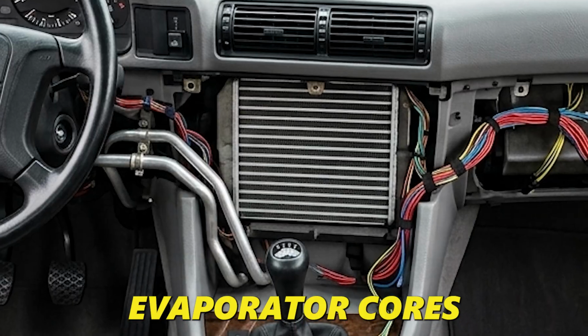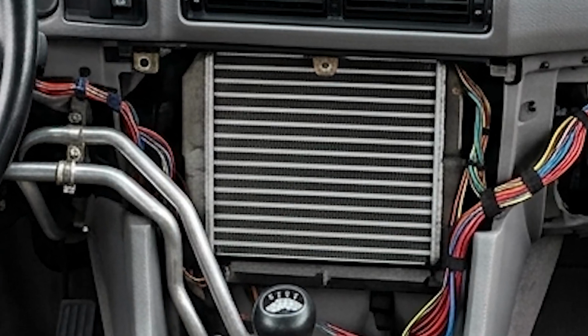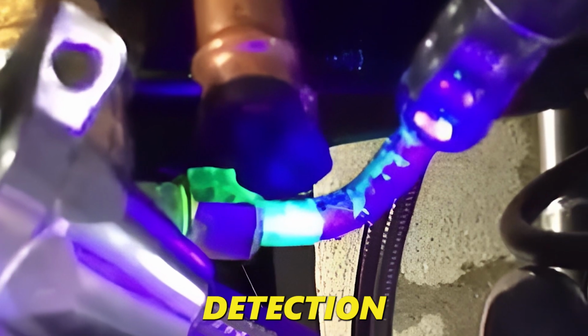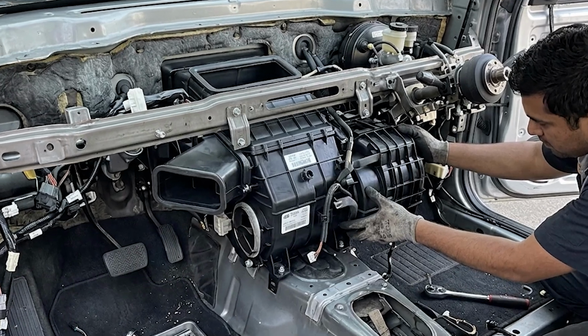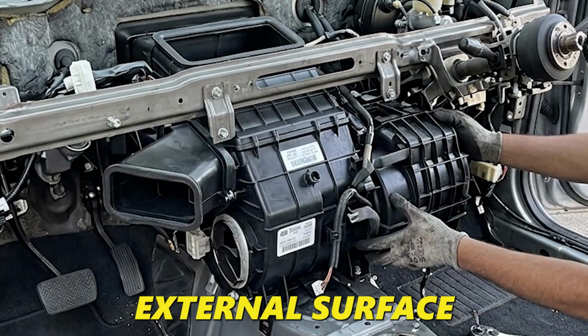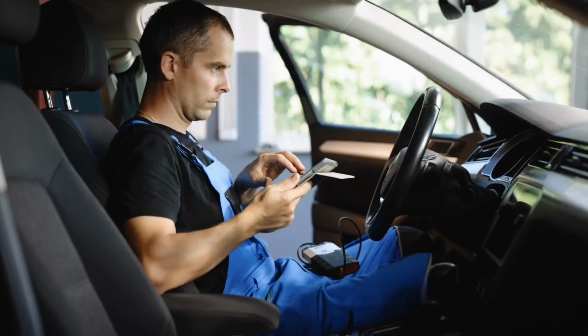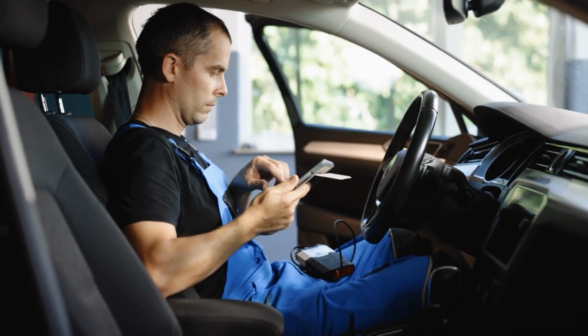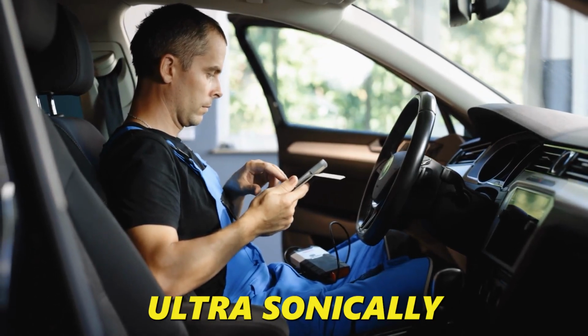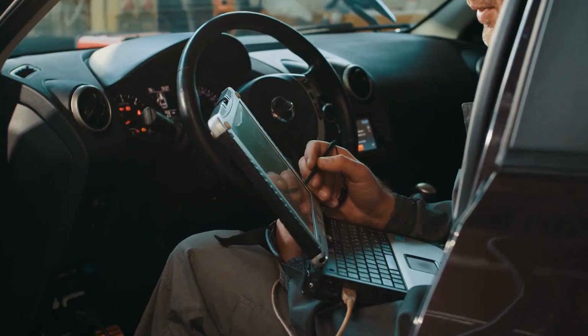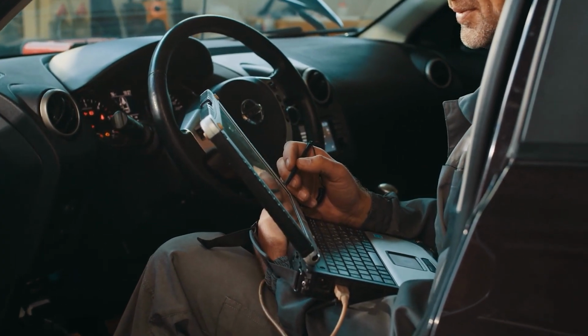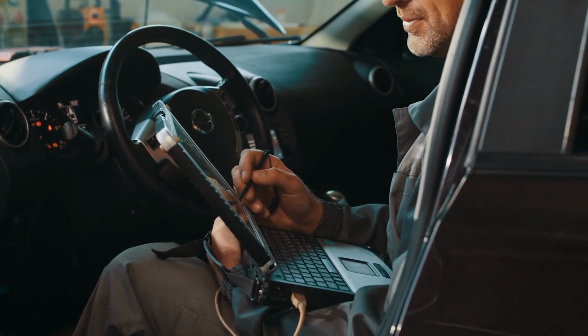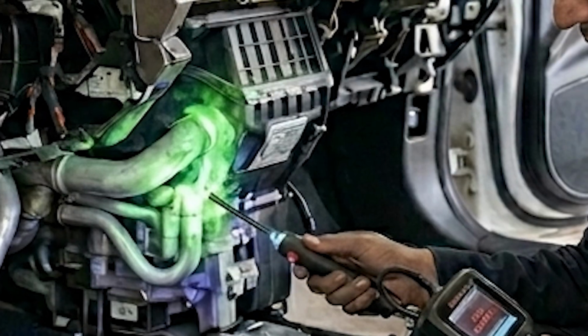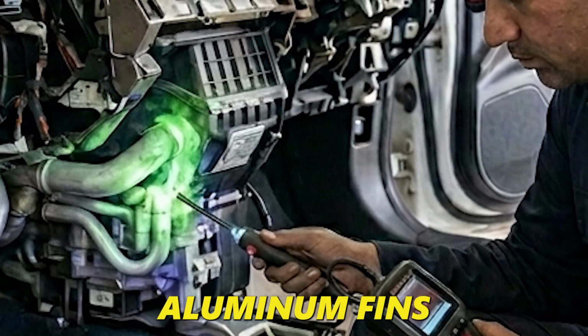The evaporator core is inside this housing, sealed from the factory. You can see immediately why standard detection methods can't find a leak in here. It's completely enclosed. There is no external surface to test. The only way to know what's happening inside is to listen for it ultrasonically or to open it. Look at this. Right here, lower corner, exactly where the ultrasonic detector pointed. You can see the corrosion bloom on the aluminum fins.